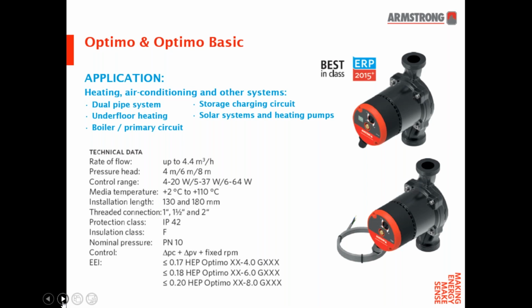From a technical point of view, they can be used where the rate of flow is up to 4.4 cubic meters an hour. Depending on the model, the pressure head ranges from 4 meters all the way up to 8 meters. The media temperature within the circulator can be from +2 degrees to 110 degrees centigrade. And the installation length, depending on the model, can either be 130 millimeters or 180 millimeters, both of which will be very compatible with refurbishment applications where you're replacing an existing circulator. The threaded connection is either an inch, inch and a half, or 2 inches. And again, this depends on the actual model.